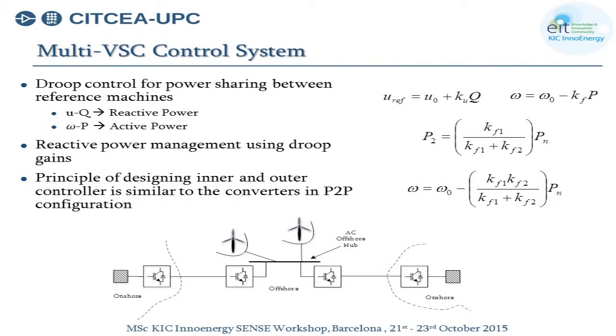As mentioned before, we have some multi-terminal configurations as well, just to transfer the power to two different locations. So if you have a multi-terminal DC system, then you need a circuit breaker. How can we avoid this situation? Because the circuit breaker is the main limiting factor in this case.